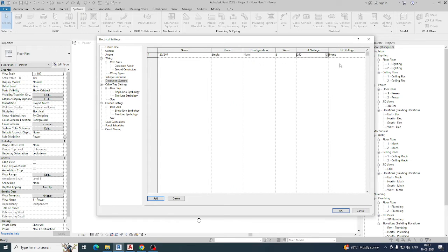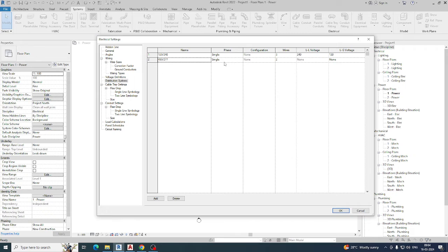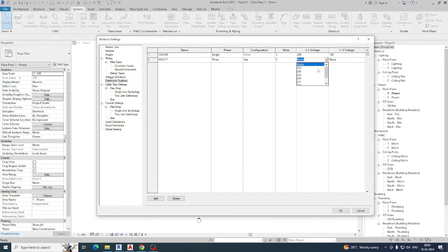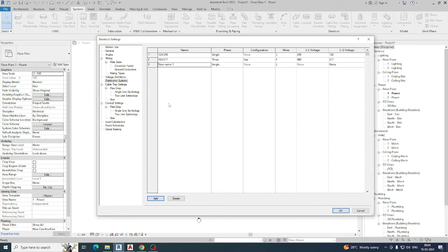Set the line voltage to 240 and the ground voltage to 120. You can also add a three-phase system — for example, 480/277. Set it as three phase, add a neutral, set the line voltage to 480, and the ground voltage to 277. Similarly, add 400/230 as three phase with four wires, line voltage 400, and ground voltage 230. Apply these settings accordingly.